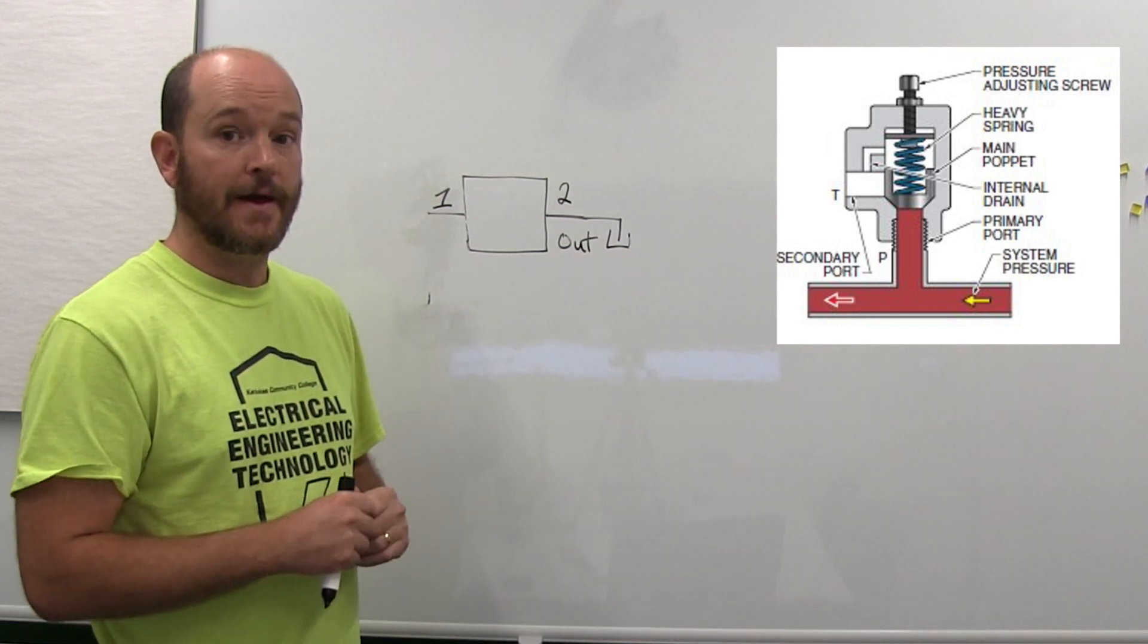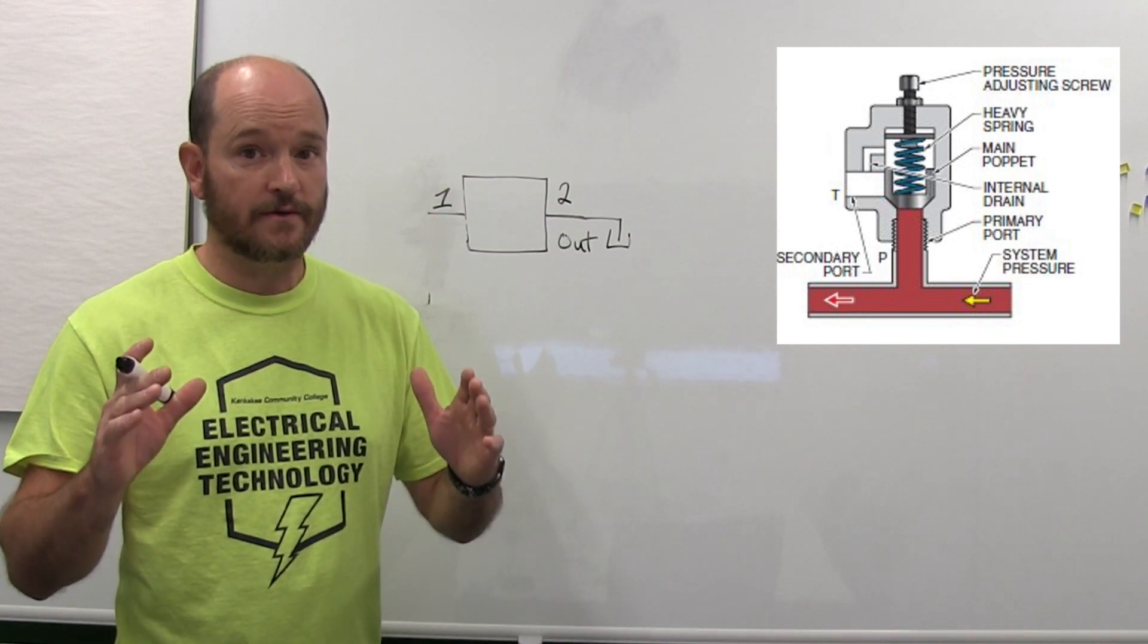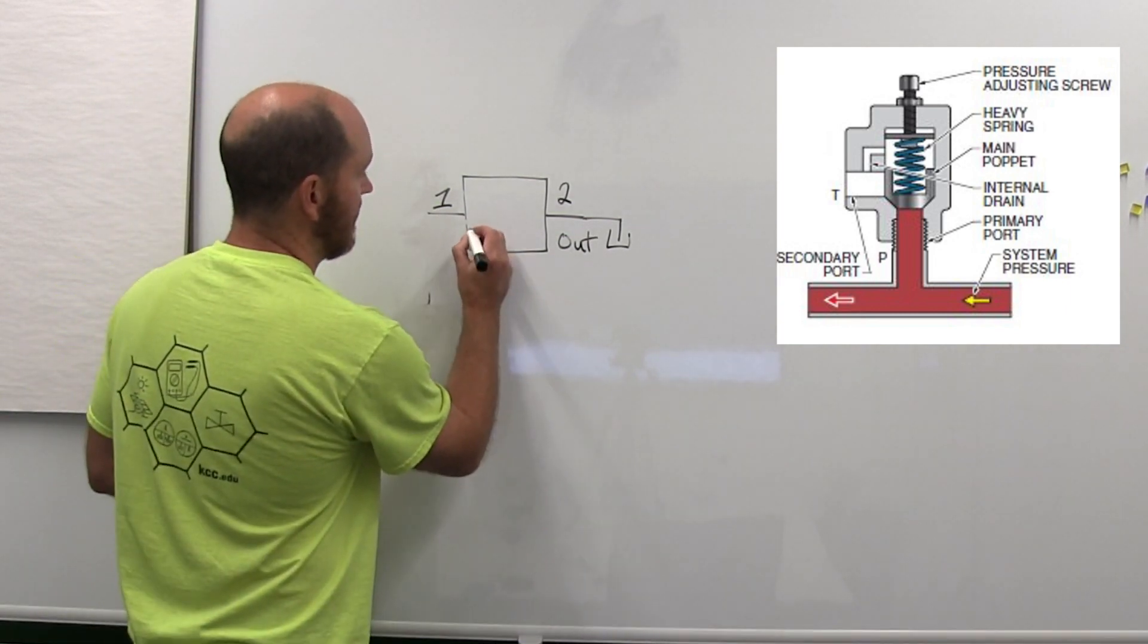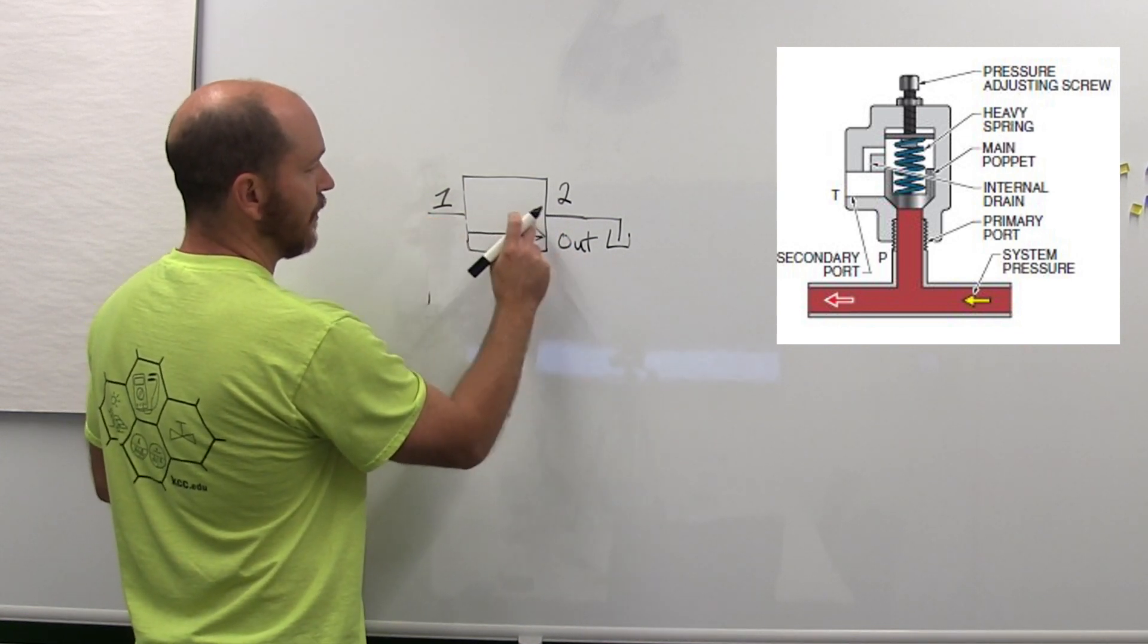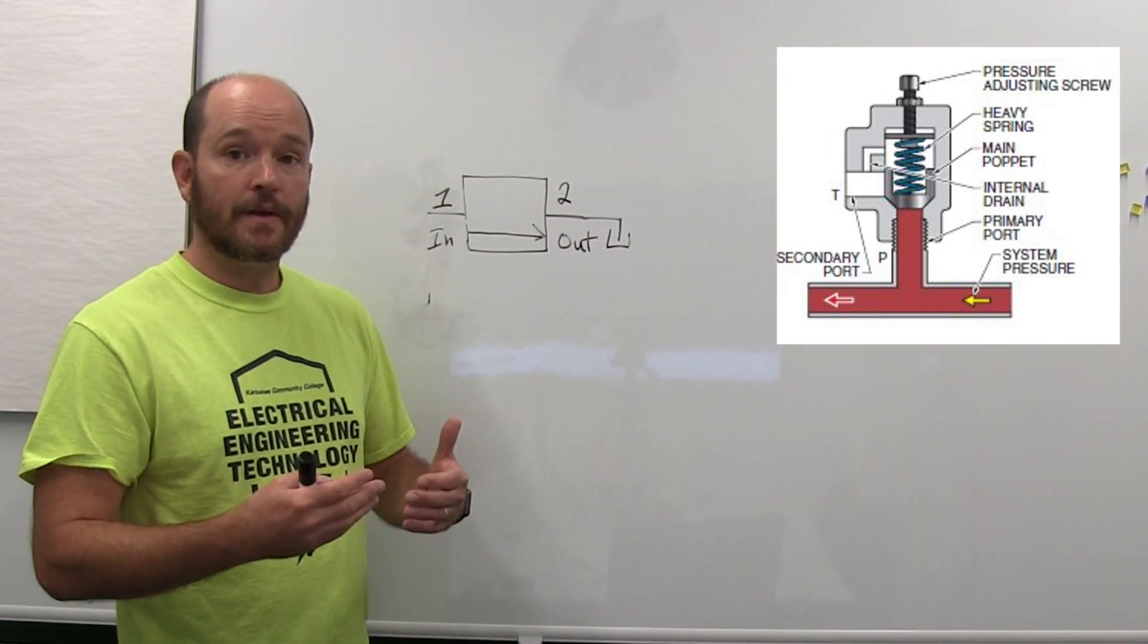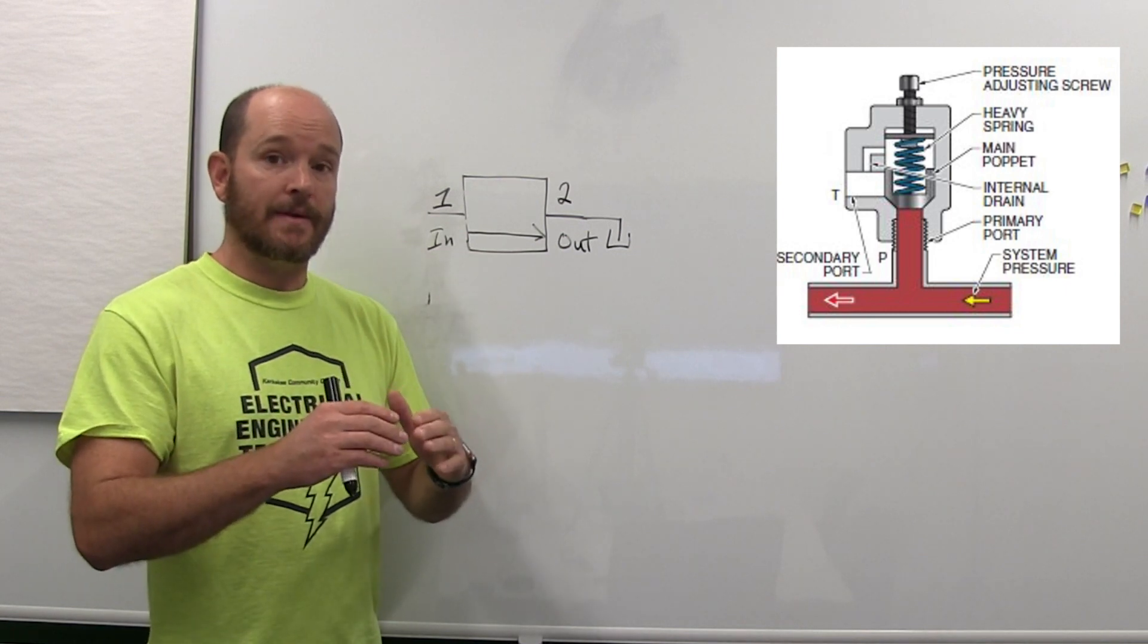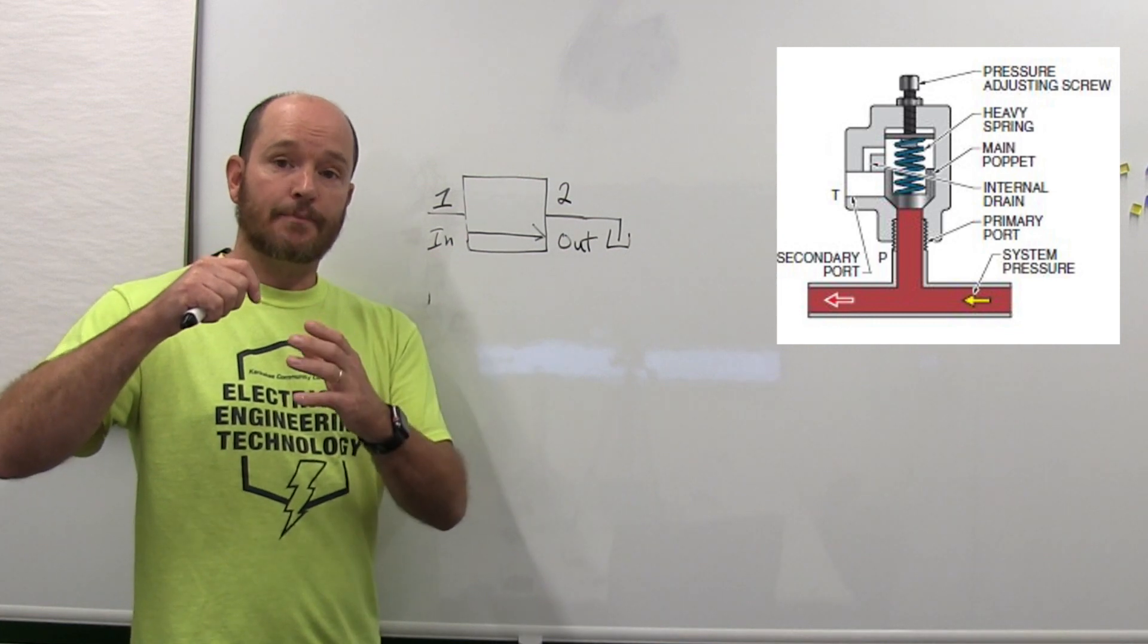The next part of a pressure relief valve is that they are normally closed valves. The way that is represented in this schematic diagram is with an arrow that is not lined up with the input and the output. If this was a normally open valve, the poppet would be in line, but this is normally closed.